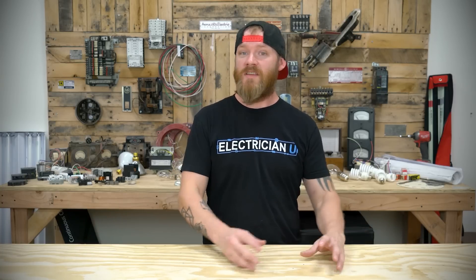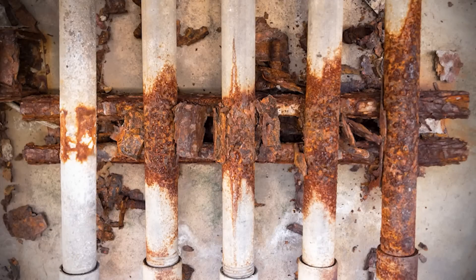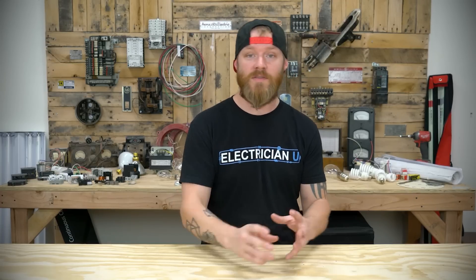Section 358.14 talks about dissimilar metals, which is really important. Anytime you have different metals, one is going to be more active and one more passive — one acts like an anode and one like a cathode in a battery. The more passive metal causes the more active one to corrode, giving up electrons and oxidizing until it separates the connection or breaks down entirely. Aluminum EMT is a very active substance, so it will degrade when introduced with other metals. You have to be careful what straps, couplings, and fittings you use.